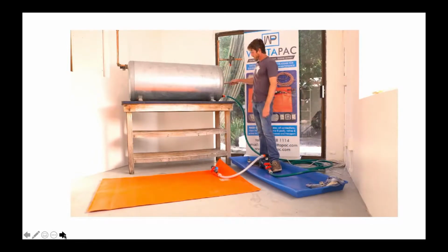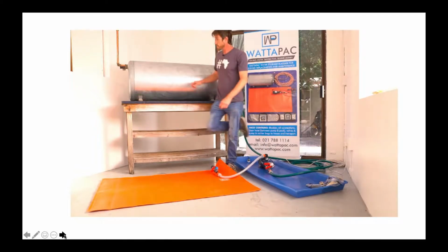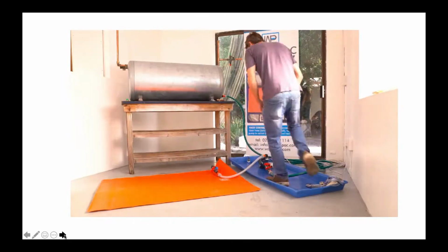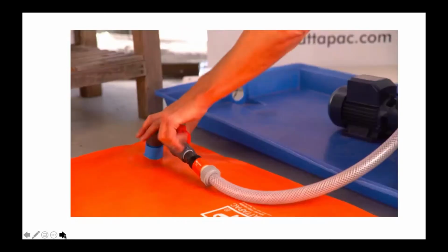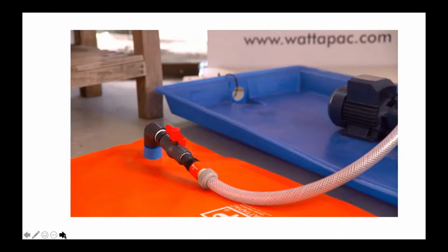The copper pipe will then get placed into the drain cock and tightened up. Once you've done that, you're going to take the hot water vacuum breaker off, and the siphonic process will happen naturally through the pump into the bladder. So once the copper pipe is inserted into the drain cock, we simply remove the vacuum breaker, and siphonic action will immediately take place, and water will drain into the bladder in about 7 minutes through the pump. And the water should naturally start flowing through the system.